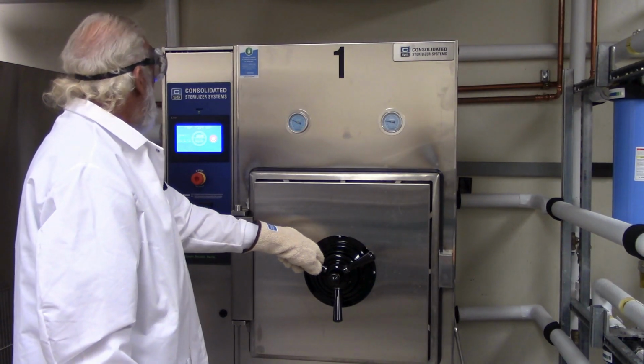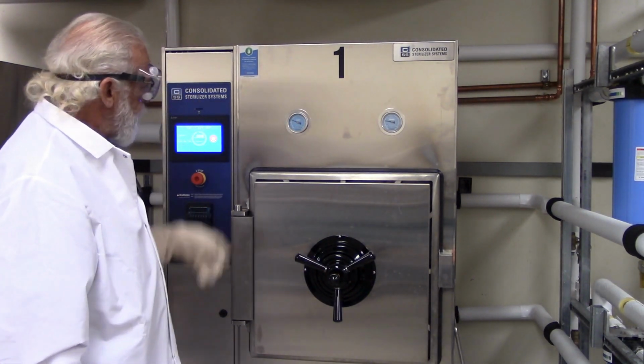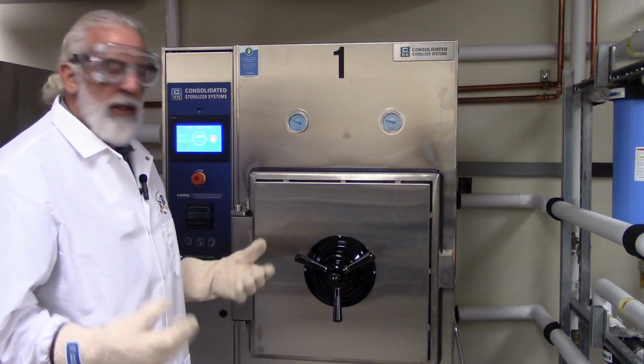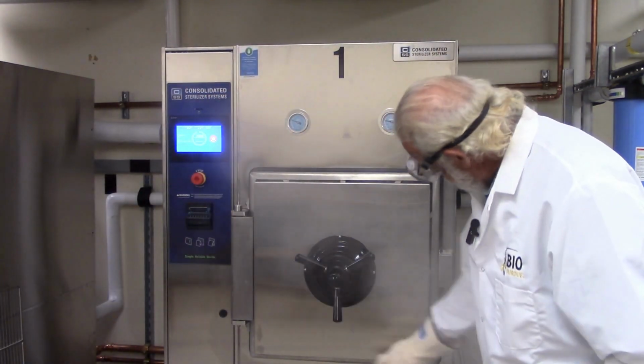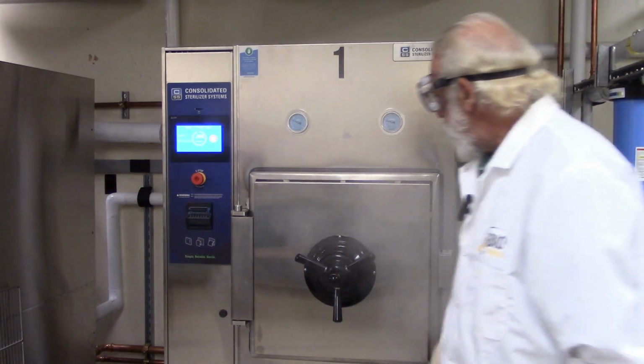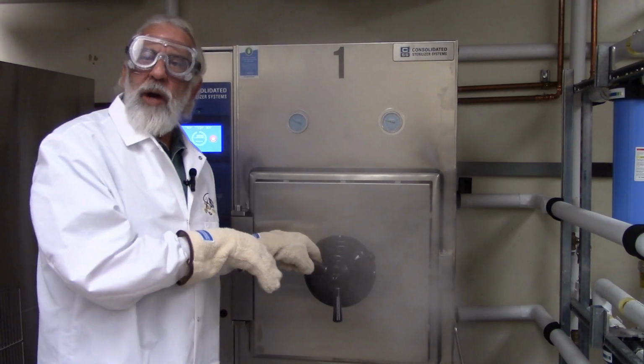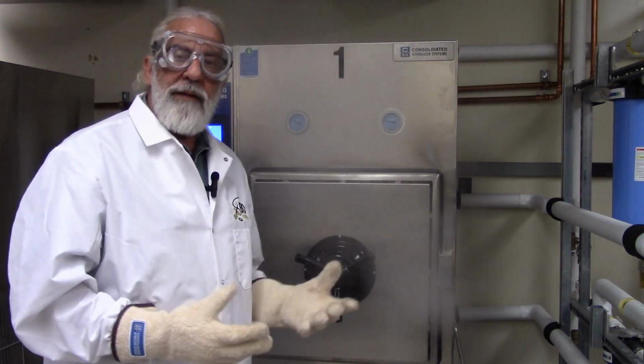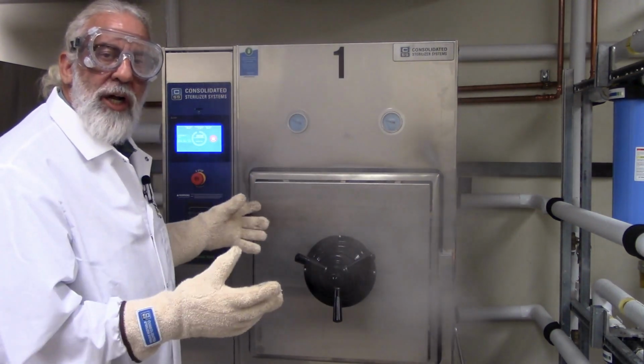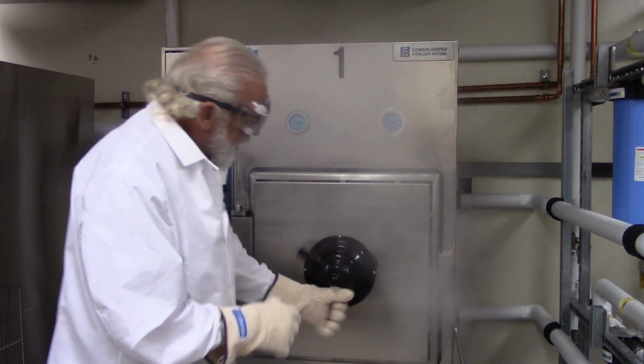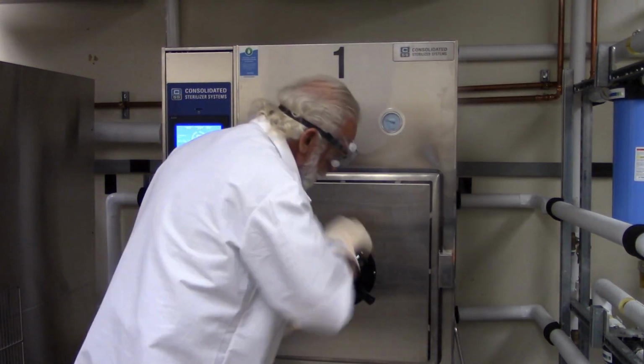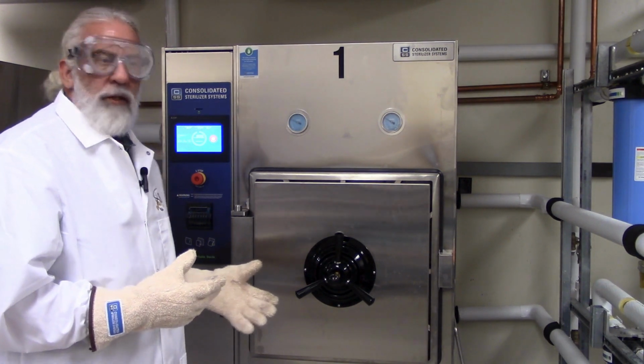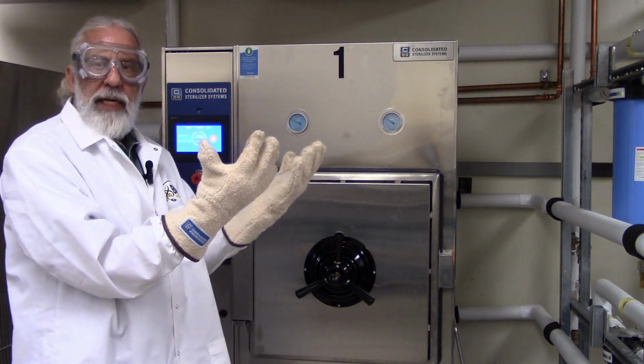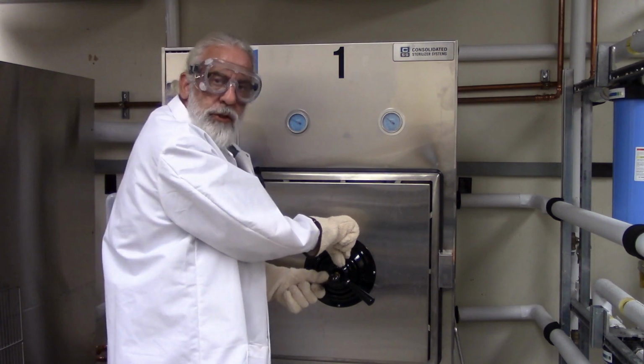Now, typically, you'll start to hear, it sounds different, so you can hear that steam, something's leaking. You probably can even see at this point where it's coming out around the frame. Do not call the fire department, all right? If you're really afraid, you hit that button there and it'll shut it all down. But what it really needs is it needs to be tightened. And we're good to go. So, especially with PPE on, don't hesitate to try to do that.